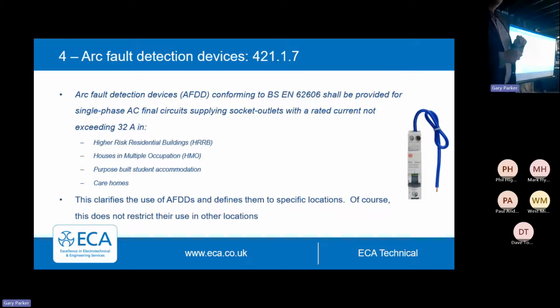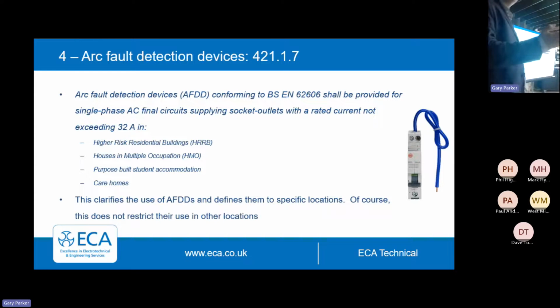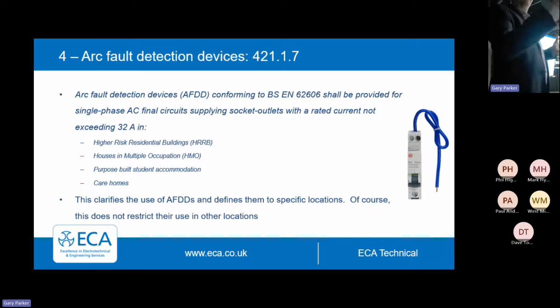One of the major problems with them is, firstly, they need a minimum current to work. So it's very specific: socket outlets. It is not a requirement on lighting, for instance, because the load on a lighting circuit will not be sufficient for an AFDD to work. So it's pointless. You can spec them, they just won't do anything. It's a waste of 147 quid.